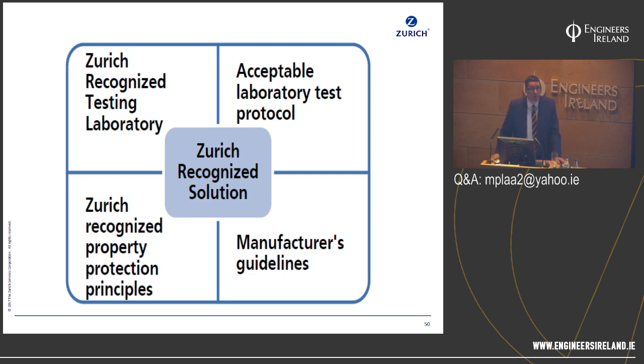So, for example, the schools are generally ordinary hazard 1, but some of the very large academies can actually be ordinary hazard 3. I have found inappropriately fitted water mist within a storage warehouse application with a 15-metre high ceiling, which would be totally ineffective. Generally speaking, in the land-based market, most manufacturers are testing to the ordinary hazard 1 protocol. Some manufacturers are now doing some limited testing on ordinary hazard 3. So the rule of thumb is that most of them, where they're specifying for schools and offices and hotels, would be an equivalency to ordinary hazard 1 fire load and occupancy.